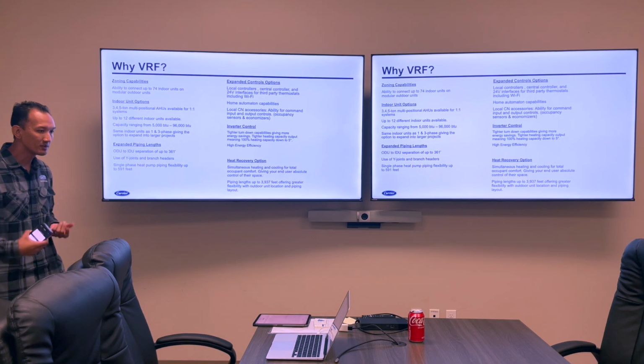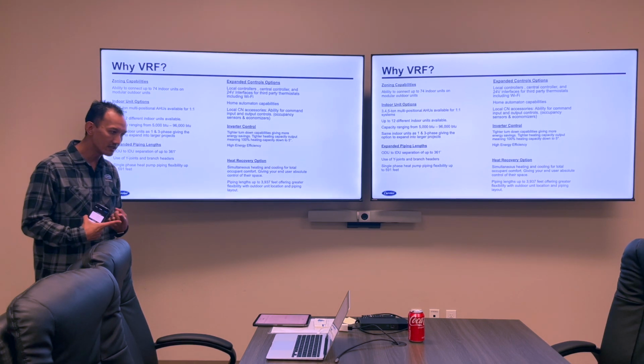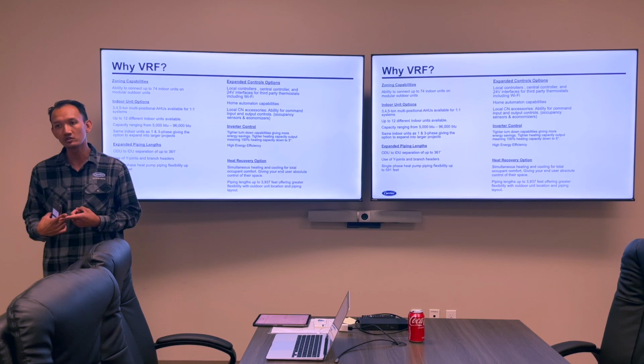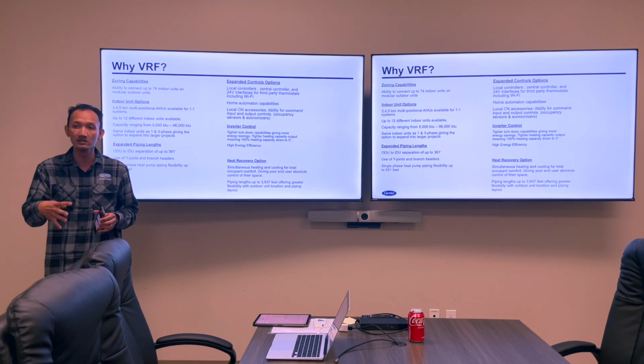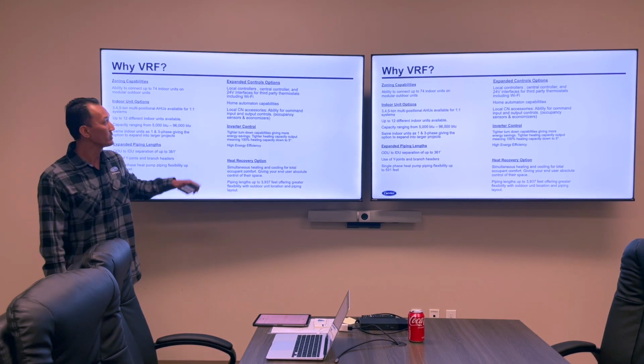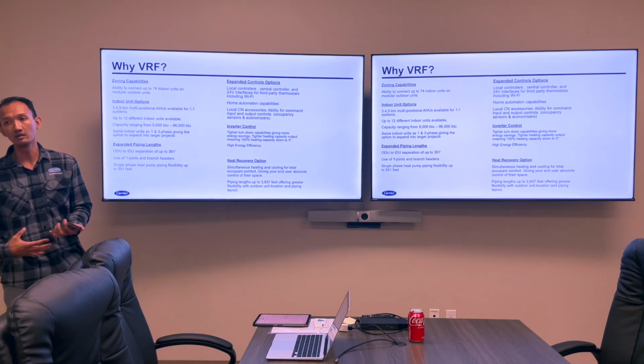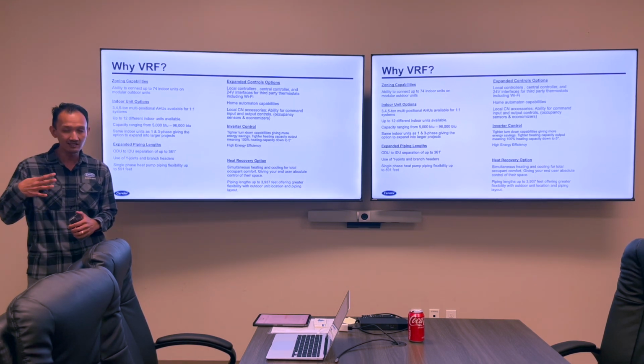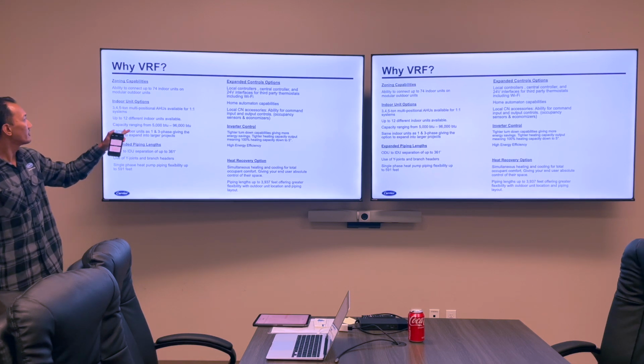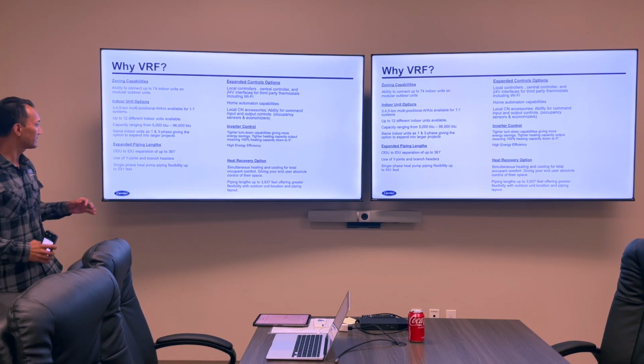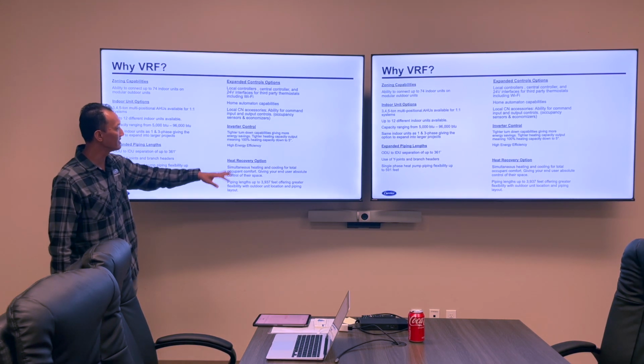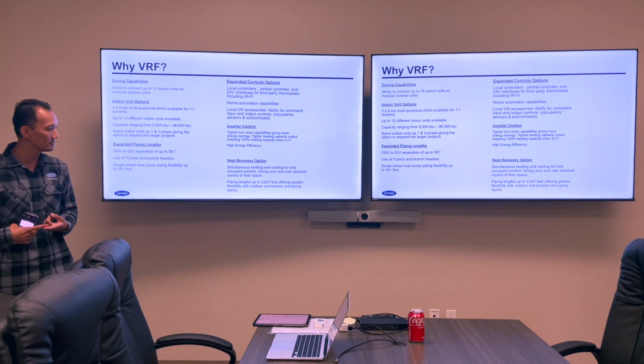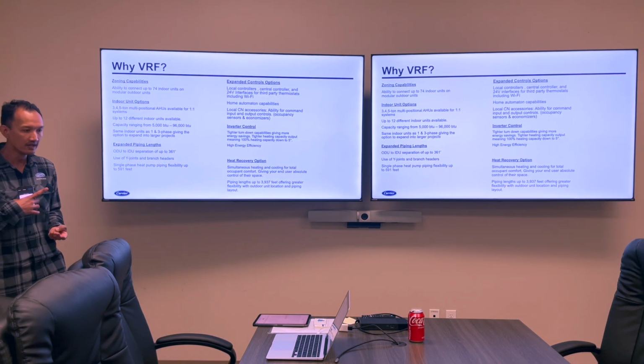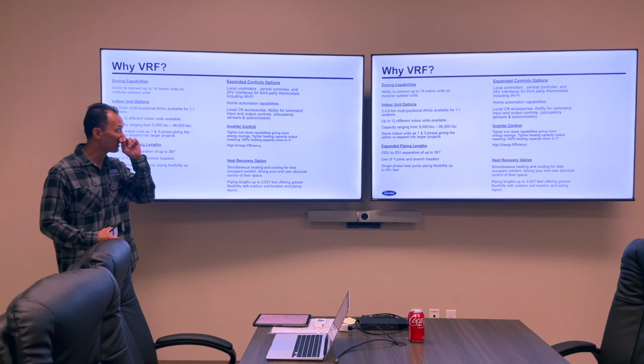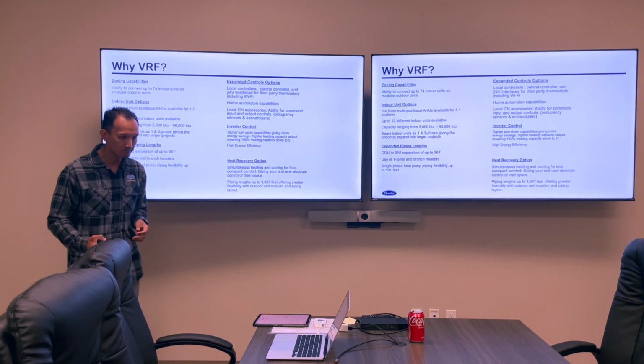We use VRF because it's very efficient. We can get precise zone control because we can place a fan coil into each zone. We can do all the way up to 74 fan coils on one outdoor unit, depending on the size of the outdoor unit. Lots of different fan coil options that we'll go over. Heat recovery, like I mentioned, and then inverter control gives us the efficiencies. We use inverter compressors, and we use EC fan motors on all of our indoor fan coils.